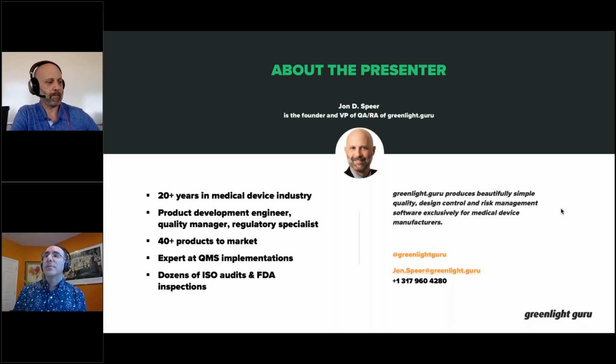Thank you. Daniel asks, how do you deal with a situation in which design controls were applied after the project started? Daniel, I wish it weren't the case, but I know sometimes that is the situation. The good news is it's absolutely better to do it, even retrospectively, than not at all. My advice is to start and develop a design and development process, capturing design controls early, because it's way easier to make design decisions as you document these things earlier versus after the fact.